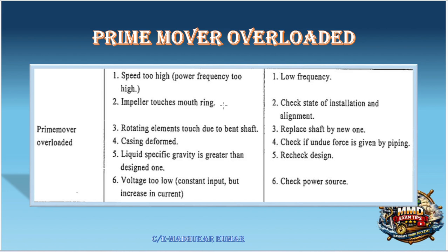So frequency is generally fixed on generators. Impeller touches mouth ring. Yes, this is a mechanical problem. So we have to make sure that when we are doing the boxing back, it is done with the correct procedure and that the proper clearance is kept between the mouth ring and the rotating element. Touch due to bent shaft. Okay, yes. Then the shaft has to be replaced with a new one. If this type of thing is there, it will draw more current, vibration, noise, everything will happen. Casing deformed. Check if undue force is being applied to the piping, means the piping attached to the pump casing is not correct and it is putting external force on the casing and due to that it gets deformed. So in that case, any touching, mechanical friction or anything will happen. So this is going to create a problem and cause motor overloading.